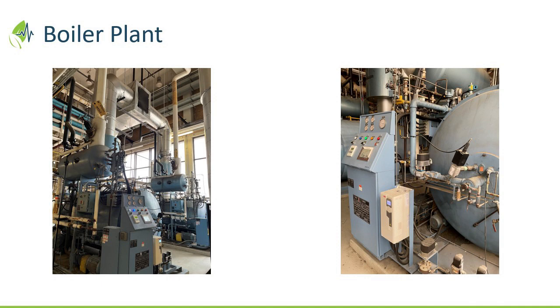So Paul's right. On those damper motors on the economizers, we had some serious problems and they weren't working. Where we thought they were open, they were positioned closed. After doing some follow-up with our technicians, we had to replace it because it wasn't even moving at the time. Sometimes it would just nudge, and you would look at it straight on and say, oh, it's open, but it's not even close. Was that the damper or the actuator? The actuator. You replaced that? Replaced it. Got it. Right now it's been working. We keep a close eye on it, and we do have temperature readings above and below, so we keep good track to make sure those dampers are functioning.